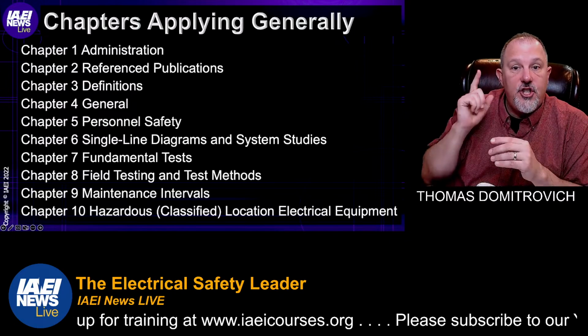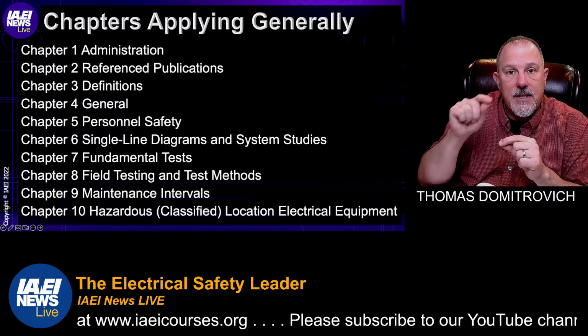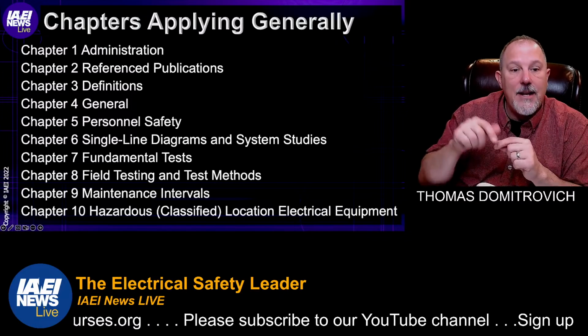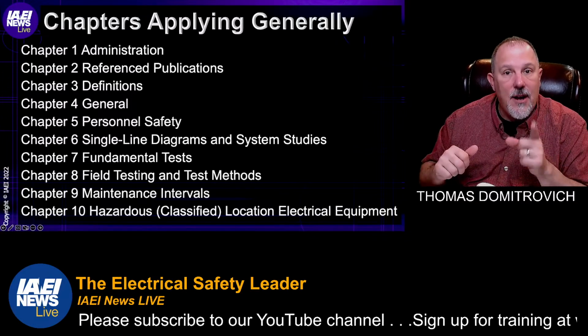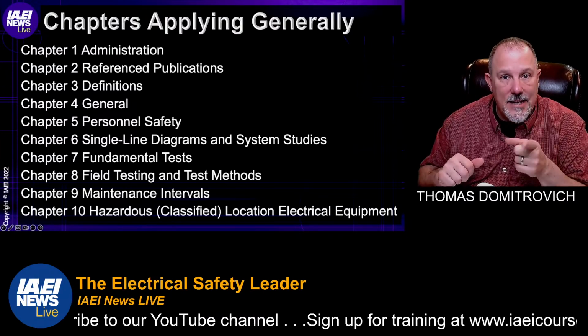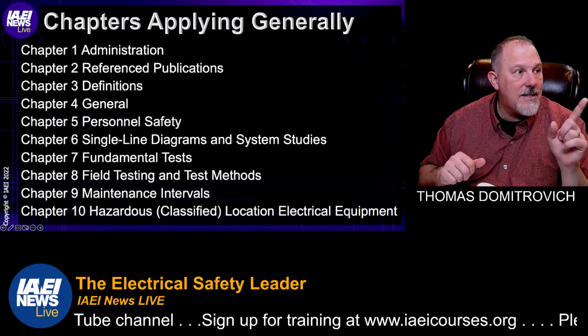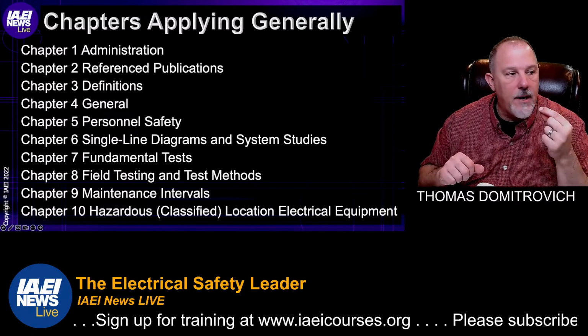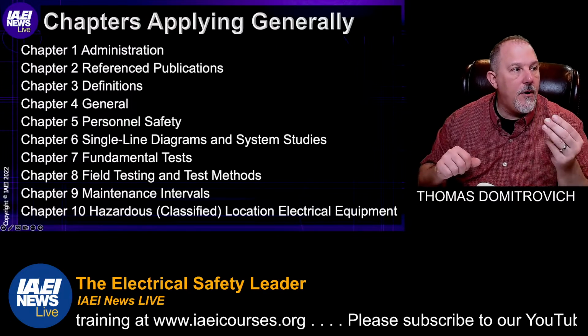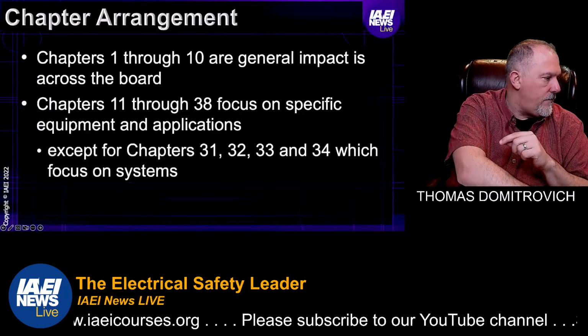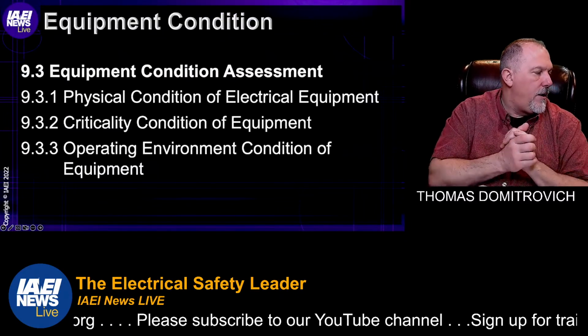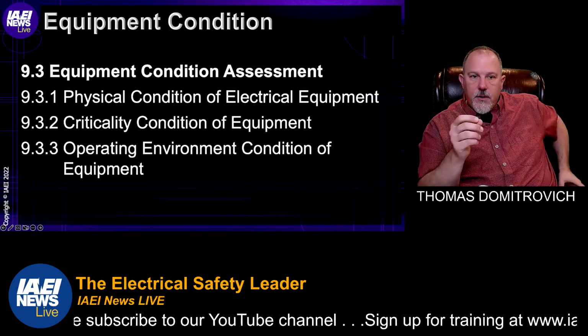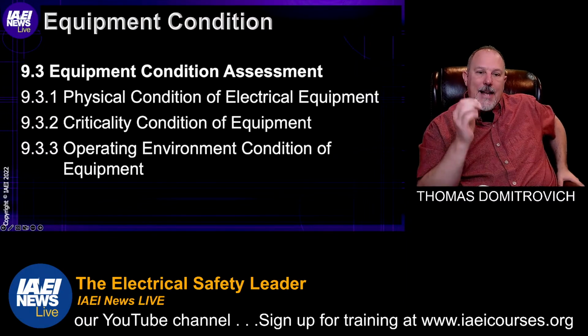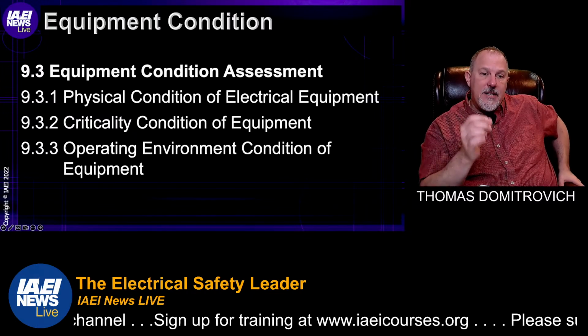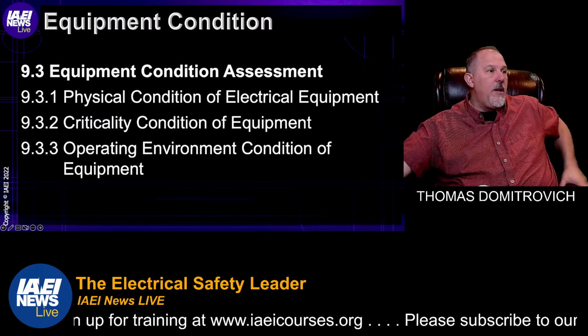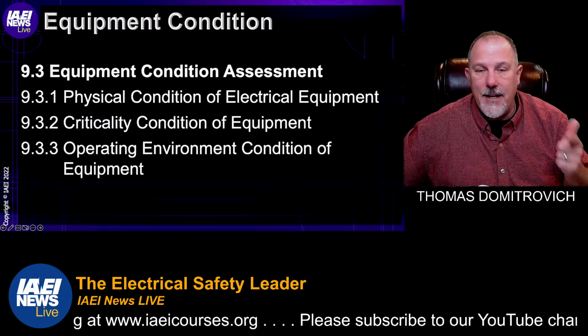So I was in chapter 4, general requirements, and it told me that my maintenance plan has to consider conditions of maintenance. Where do I find that? In Chapter 9, and specifically 9.3, Equipment Condition Assessment. So this is where I establish the condition, whether it's a condition 1, 2, or 3. And there are 3 areas in 9.3. I have the physical condition of electrical equipment, I have the criticality condition of equipment, and the operating environment condition of equipment. So, physical condition of electrical equipment, equipment that is included in the EMP.